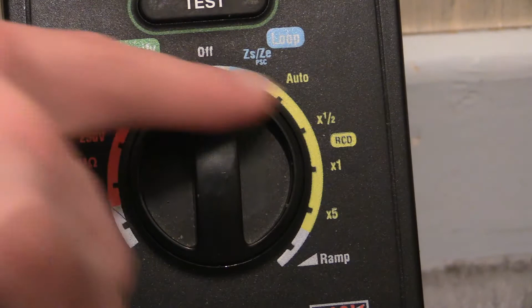So say for example on the times 1, if I rotated this right the way around to the times 1 and then pushed the test button, it would say the RCD tripped in 29 milliseconds or something like that. I don't think it'll tell you what current it tripped at. It just says 29 milliseconds and that's it. If you want to know the actual current that the RCD tripped at, you use the ramp function. You turn this right the way round to here, and then push the button, and it will slowly go up and up and up. And when it trips off, it will say on the display the amount of current it trips at. So that's all the features and functions it can do.